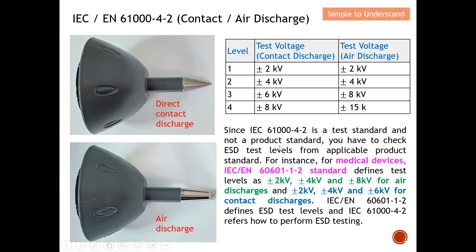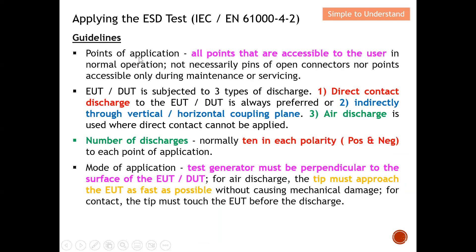Next, let's go through guidelines on how to apply the ESD test. Regarding the point of application: all points accessible to the user need to be tested to ensure robustness against ESD. This includes all points accessible during normal operation, not necessarily only open connectors or points accessible only during maintenance or servicing. In short, whatever points are accessible to the user, you must perform the ESD test.